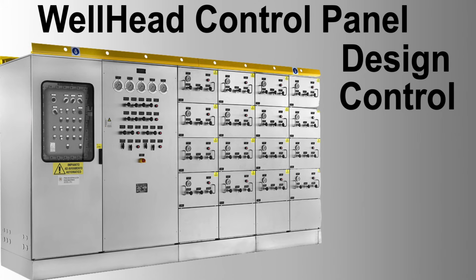Surface safety valve SSV control loop. Function: the SSV is installed at the wellhead to provide a quick shut-off mechanism for the well flow. Components: hydraulic actuator operates the SSV. Hydraulic control line connects the WHCP to the SSV. Pressure transducer monitors the hydraulic pressure in the control line. PLC RTU controls the hydraulic actuator and monitors the pressure transducer.